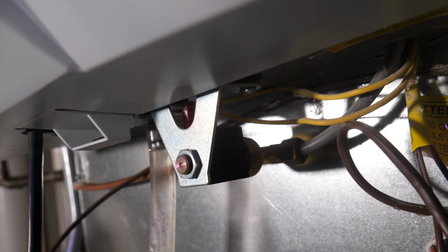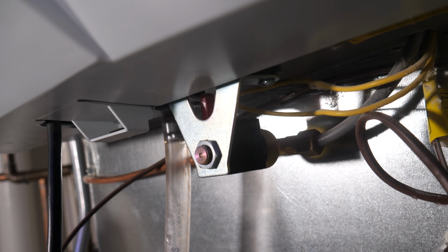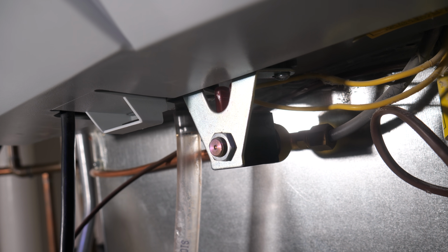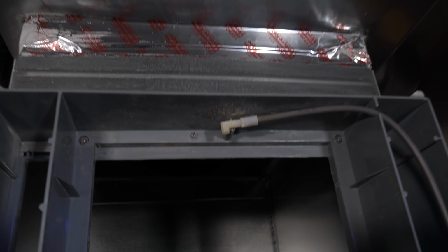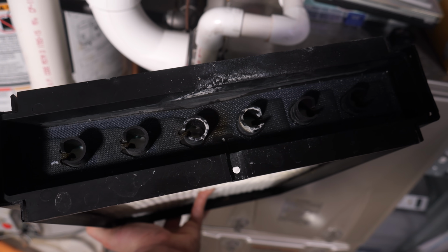Where's the water coming from? It's coming from right here. When the humidifier is running, this solenoid valve opens and a small but steady stream of water is fed through this line and up to this nozzle, where it's then distributed through these drip holes and onto the pad.